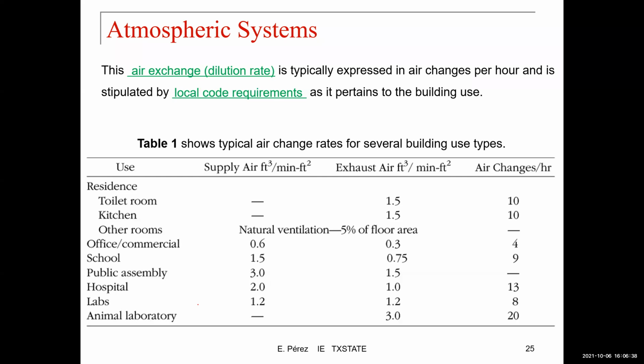Office commercial, it has other requirements. For school, you see that start increasing. For public assembly, goes higher, more people. Hospitals, 2. Labs, 1.2. And that's for the supply, and here's for the exhaust. So for an animal laboratory, you'll see that that is pretty high when compared to the other examples. So again, these are typical air exchange or change rates for several building use types.